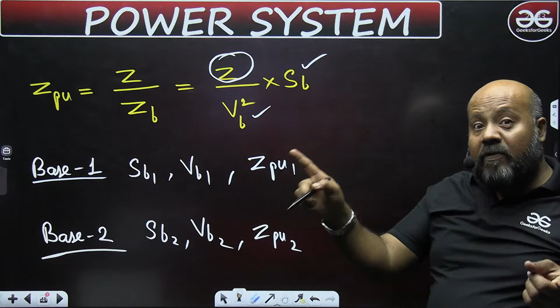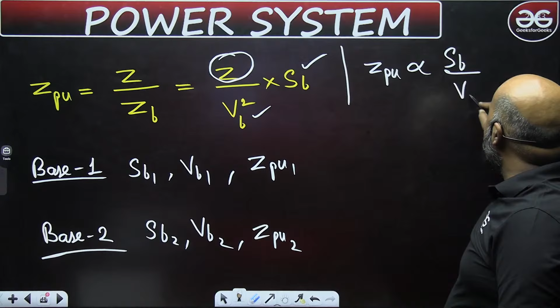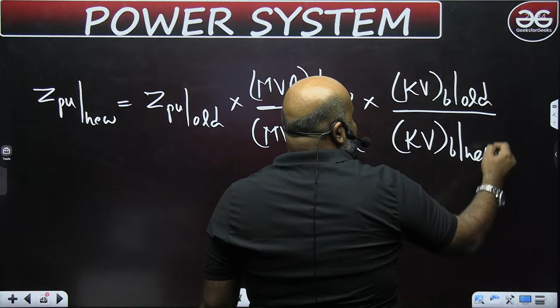So can I write that the per unit value of impedance is proportional to SB upon VB squared? Yes. Using this, you can write: Z per unit new equals Z per unit old multiplied by (MVA base new upon MVA base old) multiplied by (kilovolt base old divided by kilovolt base new) squared. This is the general expression for transforming a given per unit impedance from one base system to a new base. Is it clear for everybody?